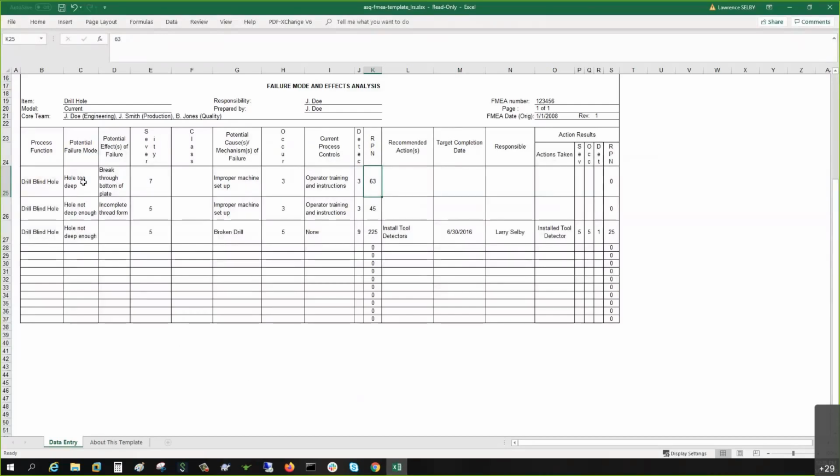So you have a row, and this could be your risk, and you have a failure mode, the effect of the failure mode, and here's your severity, your occurrence and detection, and your RPN is the multiplication of these three different fields. Then what's your recommended action and who's responsible. A lot of companies track it in spreadsheets still to this day.